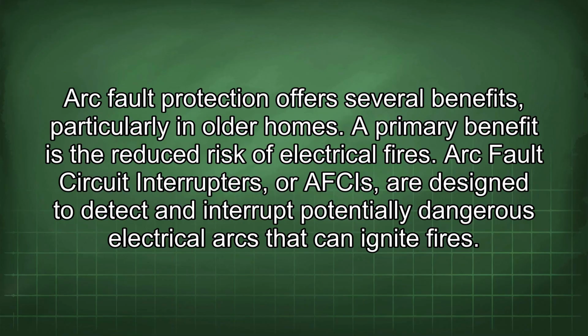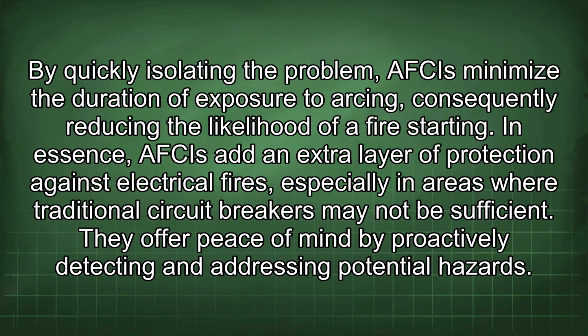Arc fault protection offers several benefits, particularly in older homes. A primary benefit is the reduced risk of electrical fires. Arc fault circuit interrupters, or AFCIs, are designed to detect and interrupt potentially dangerous electrical arcs that can ignite fires. By quickly isolating the problem, AFCIs minimize the duration of exposure to arcing, consequently reducing the likelihood of a fire starting. In essence, AFCIs add an extra layer of protection against electrical fires, especially in areas where traditional circuit breakers may not be sufficient. They offer peace of mind by proactively detecting and addressing potential hazards.